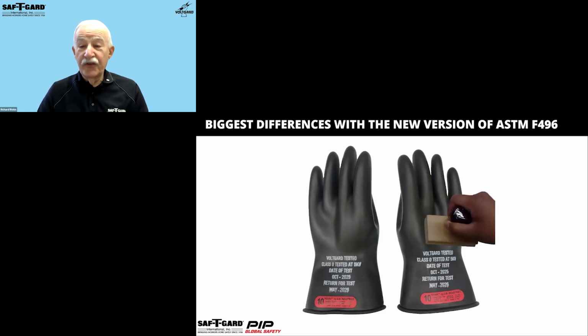Once they've passed that inspection and testing process, they're marked to clearly identify the test voltage and the test date, and then can be returned to service. It is somewhat traditional to also mark the date of test or retest so that you know that 6-month or 12-month limit. But this leaves it up to the individual worker to manage that in-service process. For example, if a company has a policy of retesting rubber insulating gloves every 3 months, then in this case, the electrical worker must be aware of when those 3 months have passed since the date of test.